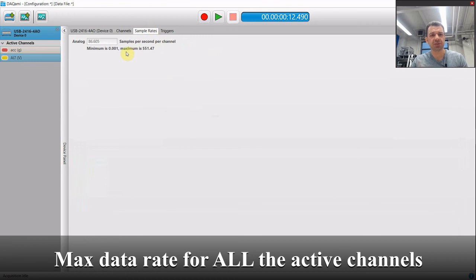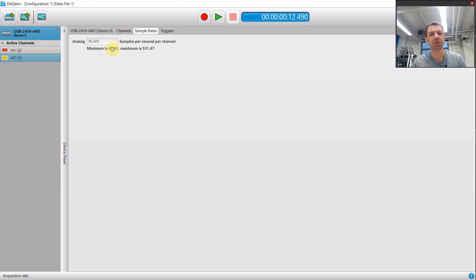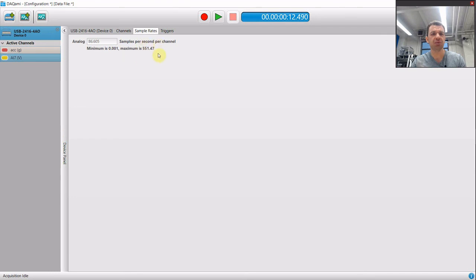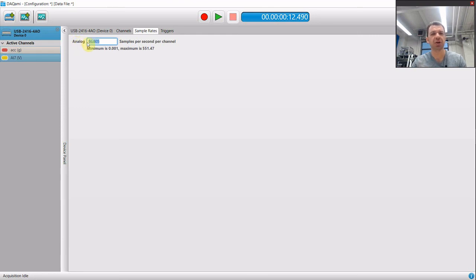Now, regarding sample rates, this instrument has a maximum sample rate of 1100 Hz for all of the channels. If you add channels, the total sampling rate will be cut by the number of channels. So in this setup, for example, we have two active channels and the 1100 Hz is cut to a maximum of 550 per channel. So you can play with this. Just remember that if you have your full 16 channels active, then the largest sampling rate will be slightly below 100 Hz.